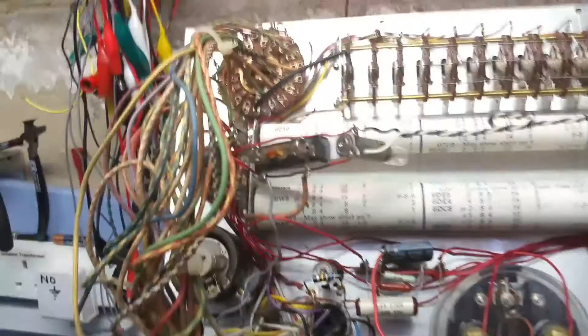As you can see, I put an inline fuse in there as well. Even though it does have a fuse for the main piece of equipment, this is really to protect the autotransformer if there's a short on the winding or anything goes wrong. It's a 1.6 amp fuse, which should be fine.